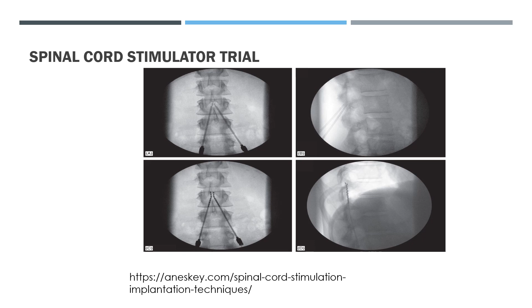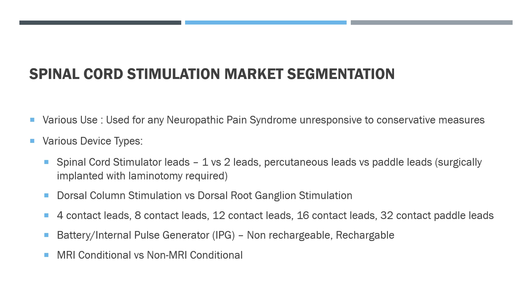In terms of market segmentation for spinal cord stimulation, there's various uses. Again, it's used for any neuropathic pain condition unresponsive to conservative measures. There's various device types within the leads and hardware. The spinal cord stimulator leads can be either 1 or 2 placed in the epidural space. There can be percutaneous leads, which are placed through the skin, or paddle leads, which are surgically implanted with laminotomy required. There's dorsal column stimulation and dorsal root ganglion stimulation. There's 4 lead contacts, 8 lead contacts, 12 lead contacts, 16 and 32 contact paddle leads. There are combination battery and IPG, internal pulse generators, which can be either non-rechargeable or rechargeable. And there are MRI conditional and non-MRI conditional hardware.